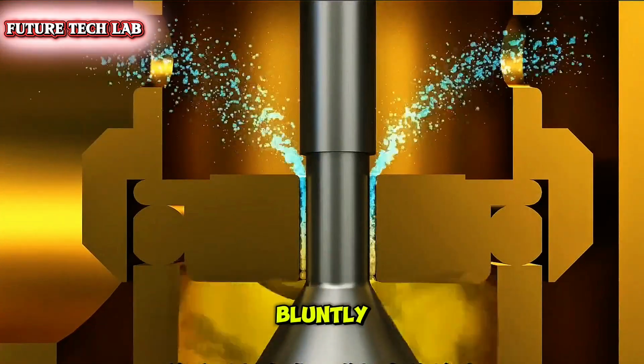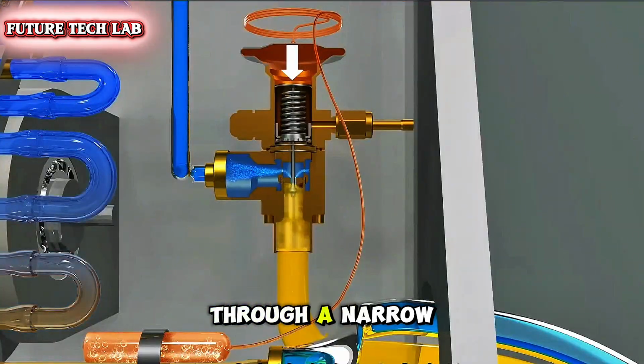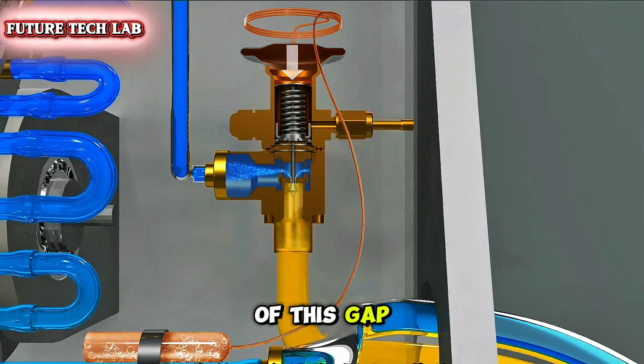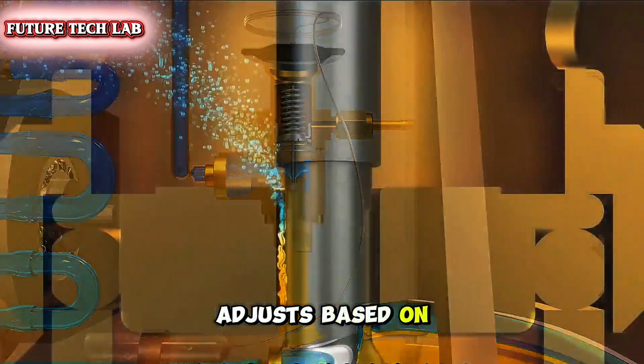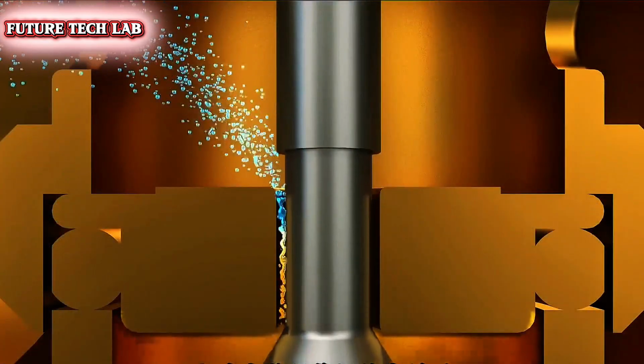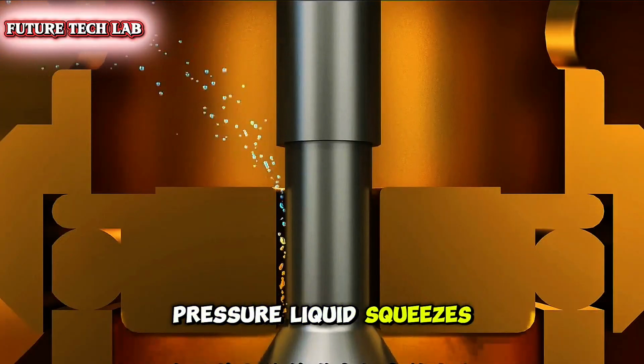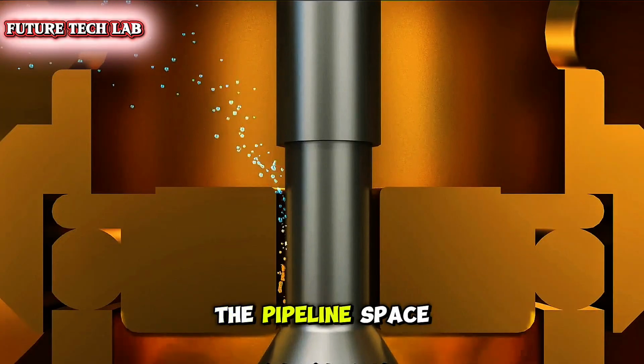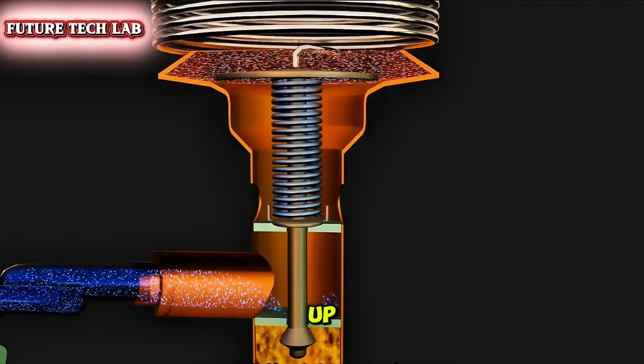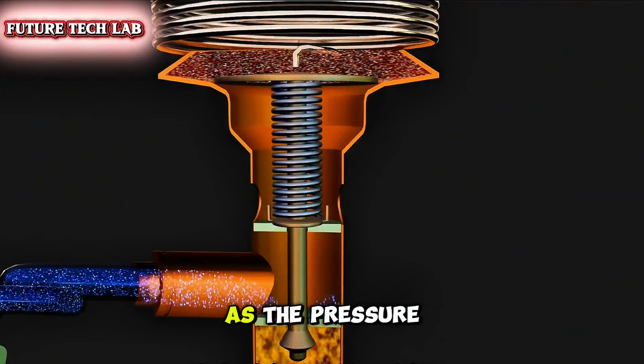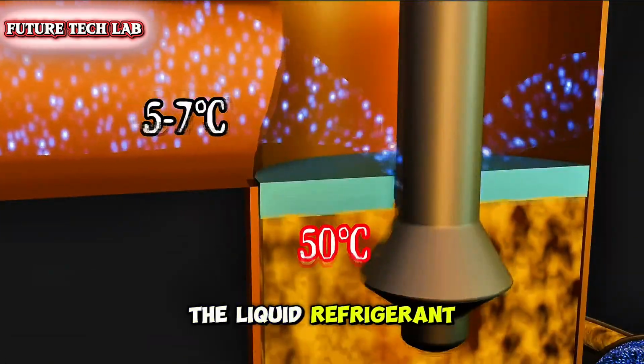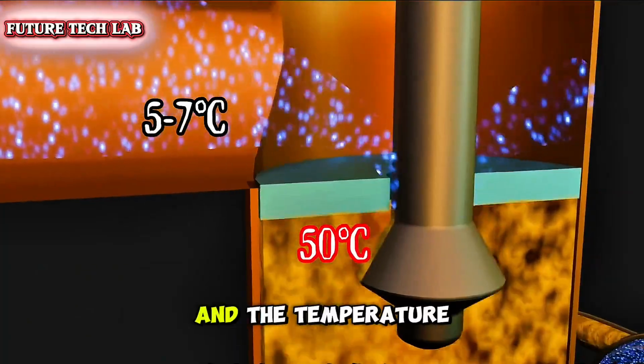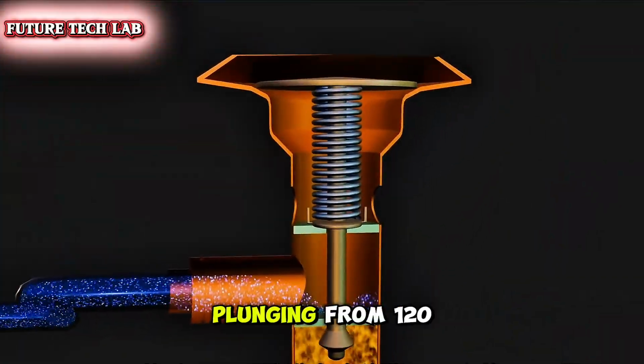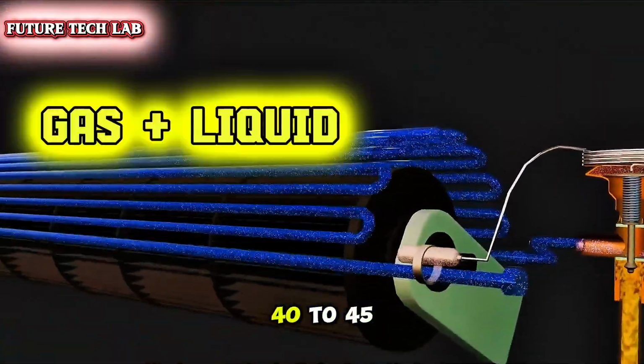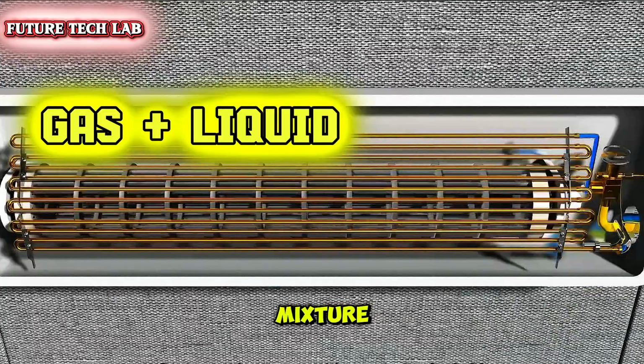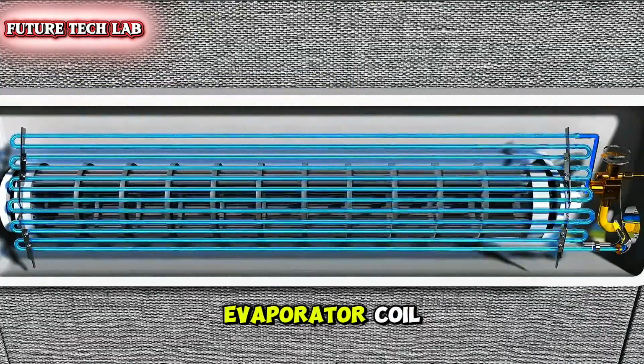To put it bluntly, the expansion valve forces the fluid through a narrow slit, and the size of this gap automatically adjusts based on thermal expansion and contraction. When this high-pressure liquid squeezes through the tiny opening, the pipeline space ahead suddenly opens up, instantly releasing the pressure. As the pressure plummets, the liquid refrigerant starts vaporizing immediately, and the temperature drops again, plunging from 120 degrees to a 40 to 45 degree gas-liquid mixture. It then rushes into the neighboring evaporator coil.